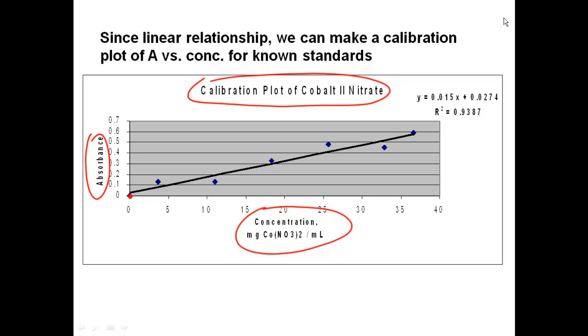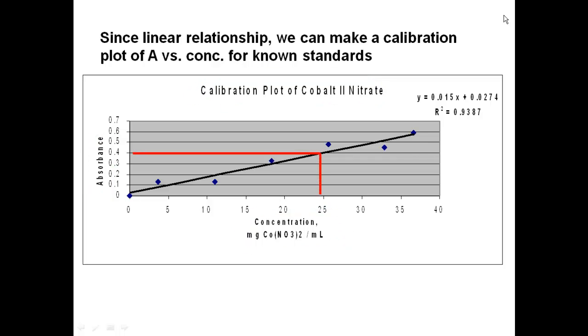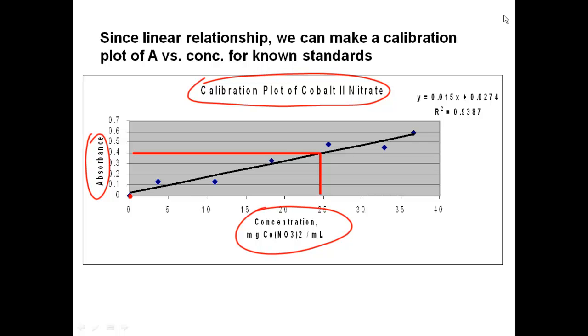Once you have your calibration plot, you can measure your unknown and get the absorbance. If the absorbance is 0.4, you go across on the plot until you hit the calibration line, then come down and read the concentration. You have to realize that concentration is that of a diluted sample. So if you want the bulk concentration, you're going to have to do another calculation, as discussed more later in this lecture.